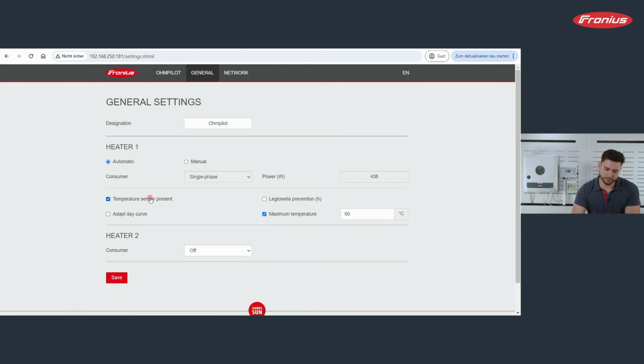The second option that comes with a temperature sensor present is a Legionella prevention. And if I activate this, I can set an hour or a period in hours in which the Ohmpilot is heating up the whole boiler above a certain threshold in order to kill all the Legionella. So it's a safety precaution, you could say. And you can set this, for example, to every 200 hours I want to do this, to heat up to above 60, 65 degrees Celsius in order to prevent Legionella. So this option also comes with a temperature sensor.